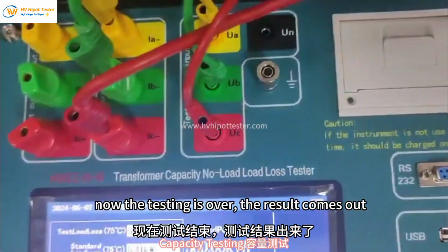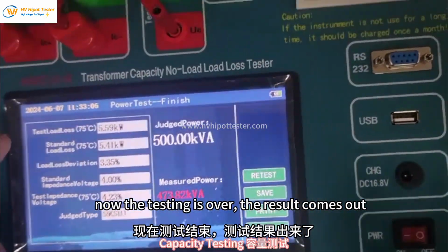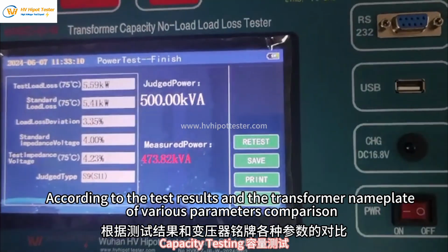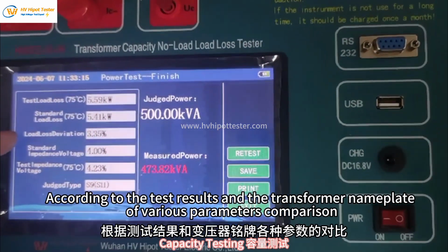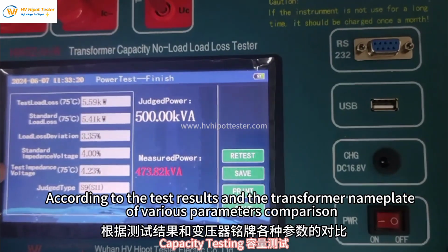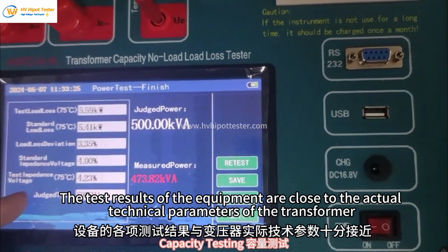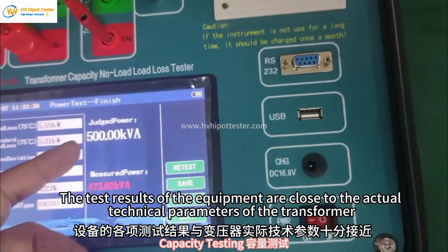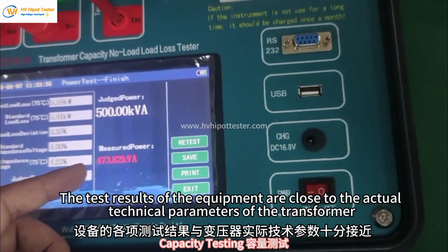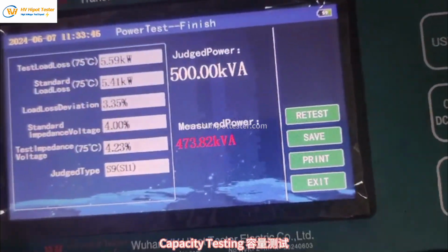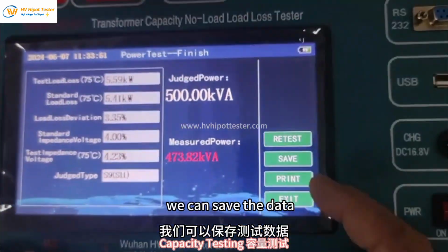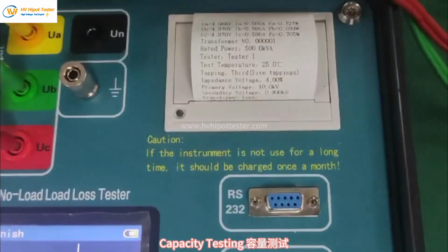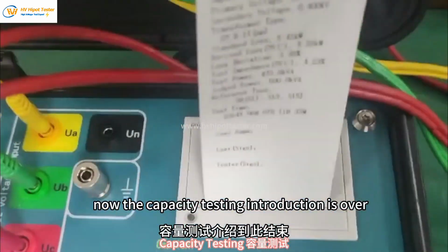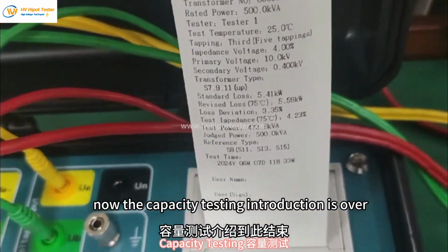Now the testing is over. The result comes out according to the test results and the transformer nameplate, with various parameters compared. The test results of the equipment are close to the actual technical parameters of the transformer. We can save the data, and also print the testing report. Now the capacity testing introduction is over.